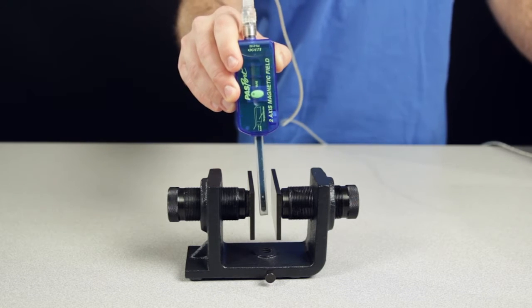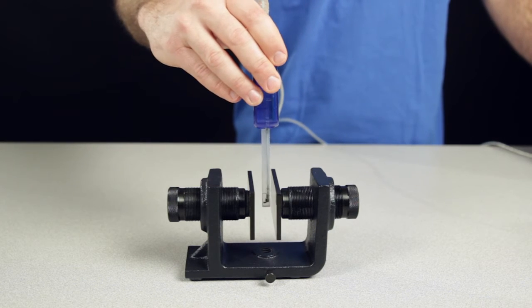Two white dots at the end of the probe mark the positions of the sensing elements. When measuring field strength, orientation of the sensor is important as the sensor is sensitive to magnetic field direction.